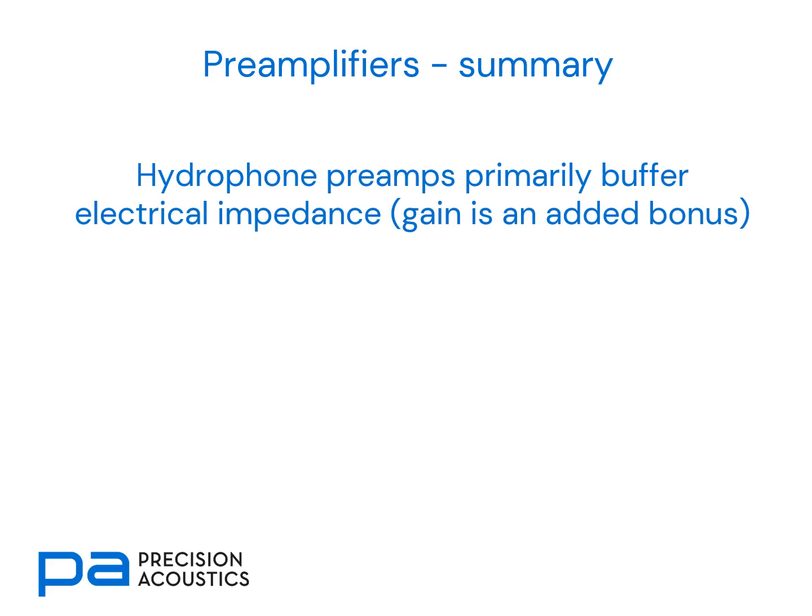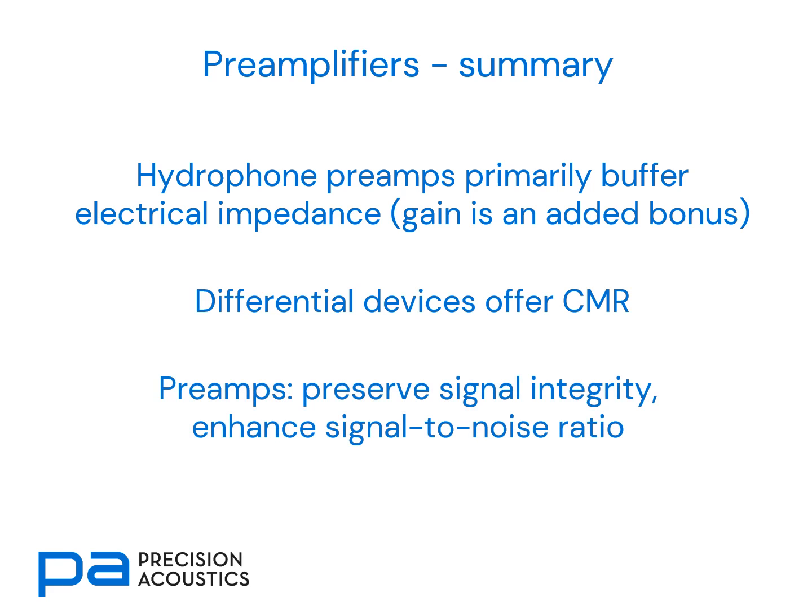To summarise: hydrophone preamplifiers primarily buffer electrical impedance, and the gain they provide is an added bonus. If the device is a differential one, we have the opportunity of exploiting common mode rejection. Therefore, preamps preserve signal integrity and enhance signal-to-noise ratio. We hope you found this tutorial interesting — if you did, come back and find some more of the Precision Acoustics tutorial videos.